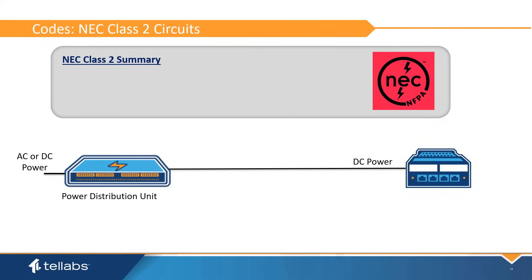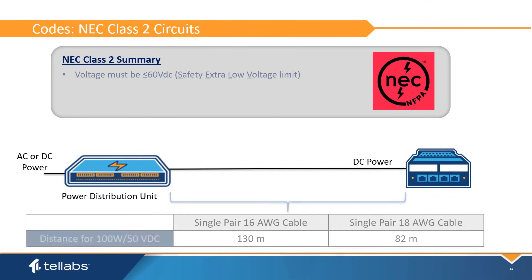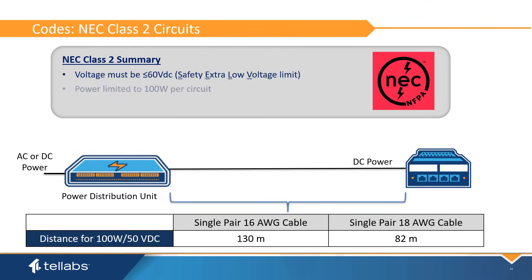To power optical LAN equipment, electrical codes must be considered. Class II power is used on most small form factor ONTs. Class II power is defined as being less than 60 volts DC and power limited to 100 watts, as defined in Article 725 of the NEC. Class II power is beneficial in the optical LAN because it does not require the same fire and safety precautions as Class I power and does not have to be installed by a certified electrician, generating significant savings when deploying optical LAN.